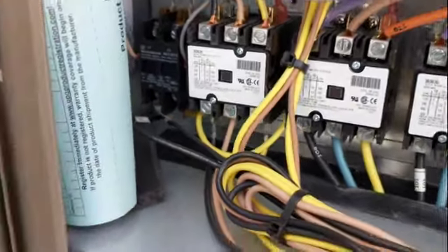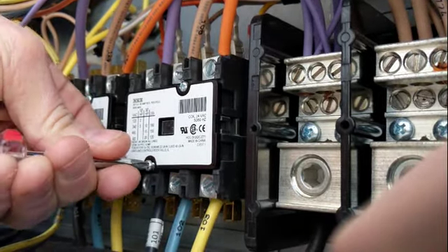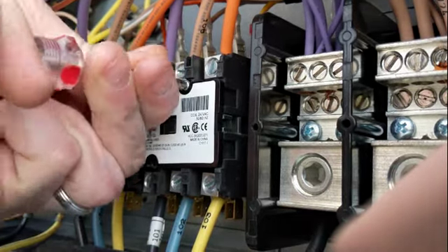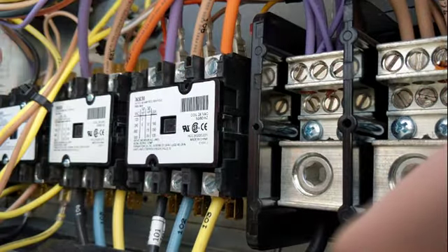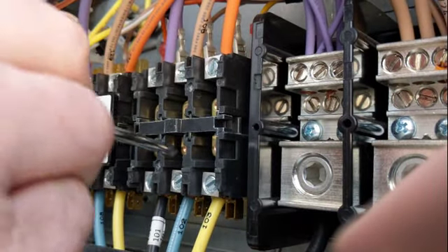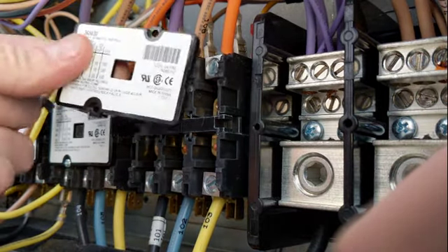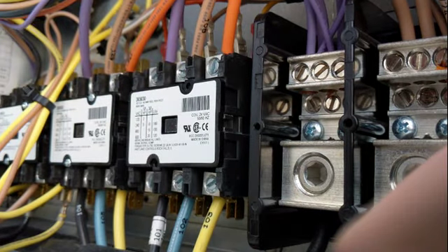Let's take a look here. Just going to look at all the contactors, check the blower, make sure everything else is good. We're definitely going to have to order a combustion blower. It's a newer unit, but it's starting to get pitted. So I think we're going to write up some new contactors.